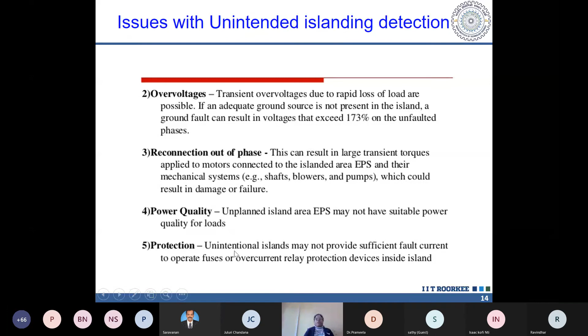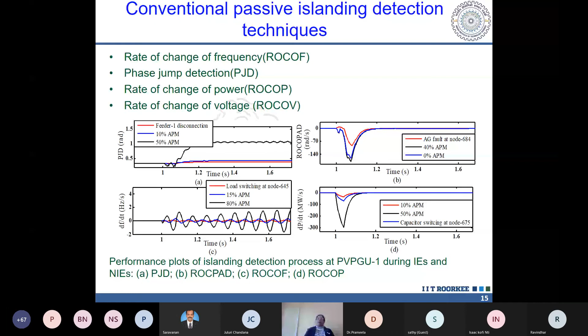Protection I have already discussed with you. There are so many conventional techniques available, like rate of change of frequency, phase jump detection, power change, and voltage change. But I will not go into detail on this because I have to cover one more new technique in this particular session. These are very conventional techniques, and I can say this much, that these techniques are actually running inside the control center. The operator is looking at what other techniques are running, and these techniques fail for the zero power mismatch condition. Zero power mismatch means that when this microgrid is disconnected from the main grid, sometimes the load inside the islanded microgrid may be equal to the power generated by the renewable source. In that case, the active and reactive power mismatch may be zero. So during that, the voltage and frequency variations are very small.